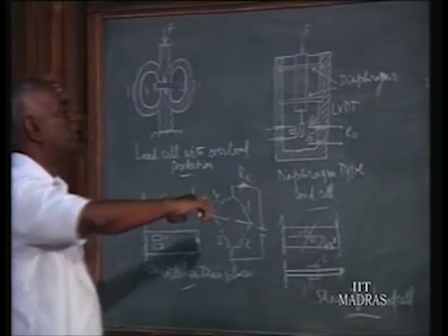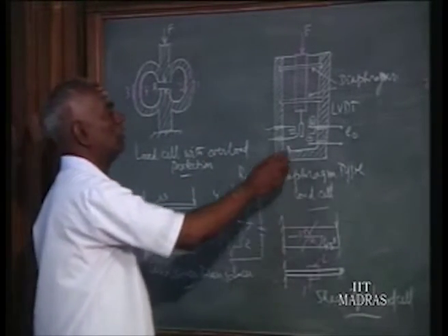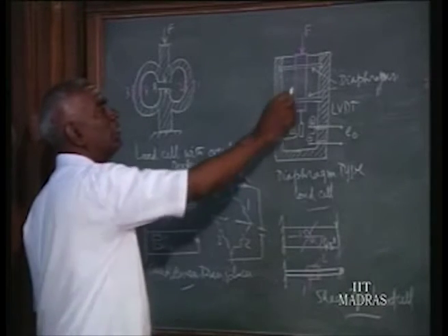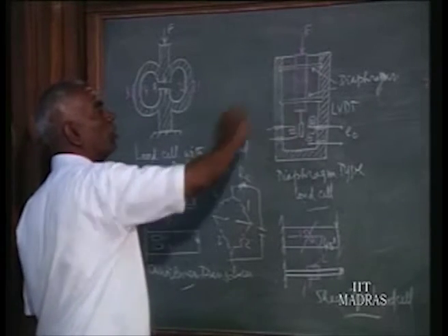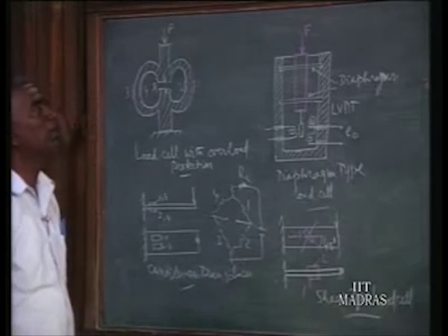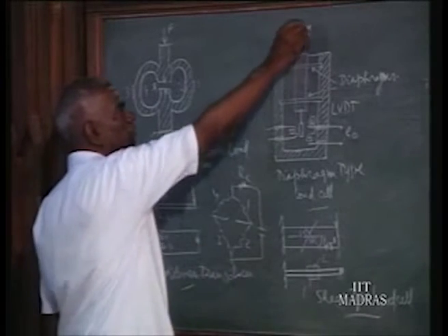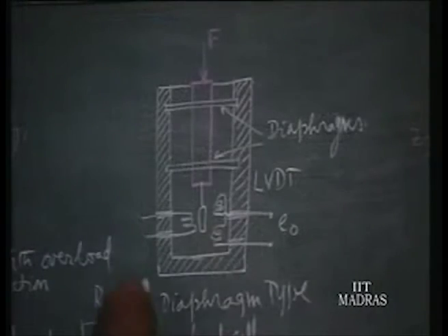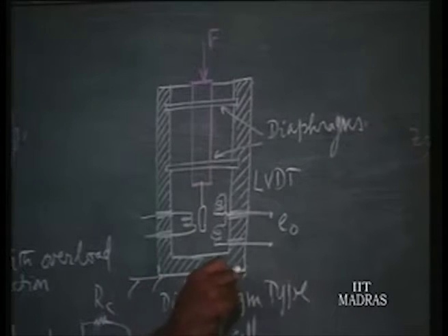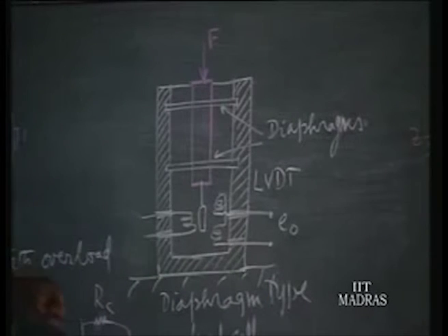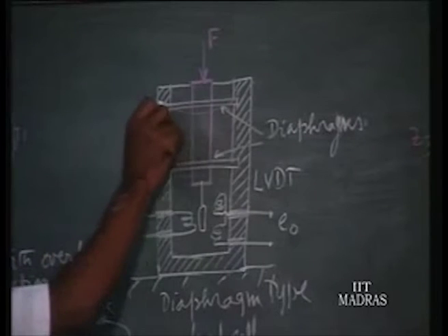Then the next one is using a diaphragm and LVDT, the diaphragm type of load cell. So two diaphragms are there, and at the middle of the diaphragm one rod is connected, and at the end of the rod we give the force which we want to measure. It can be supported on the floor. Now give the load, and the diaphragms deform like this.